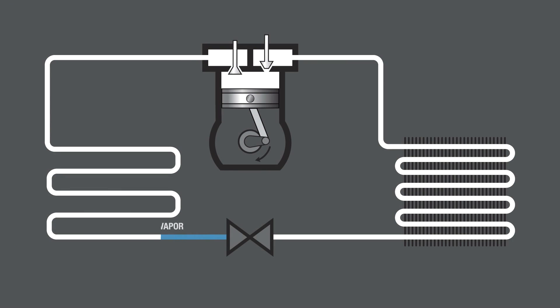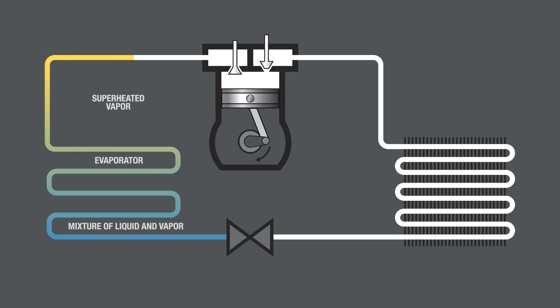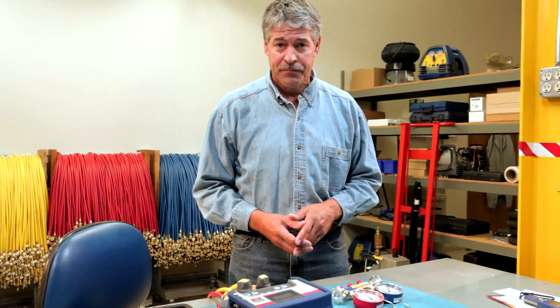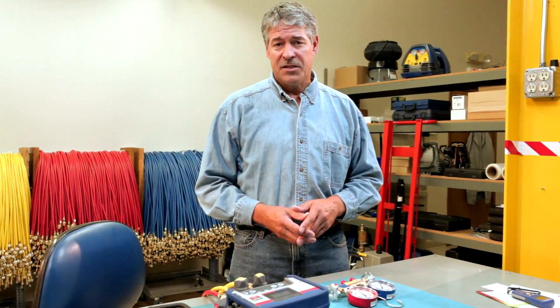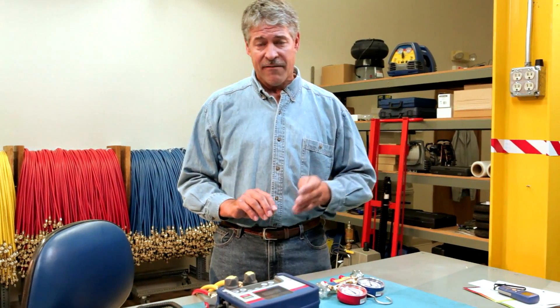As refrigerant enters the evaporator, it's in a liquid state. As heat is added to the liquid, it will turn to a vapor at its boiling point or saturation temperature. After the refrigerant has boiled to vapor, any temperature of the vapor above the saturation temperature is the superheat. Superheat is then any temperature of a gas above the boiling point for that liquid. The superheat calculation lets you know if the amount of refrigerant flowing into the evaporator is appropriate for the load.